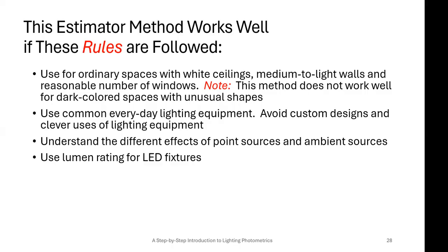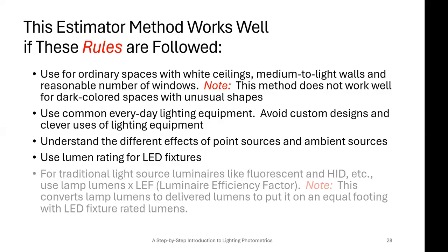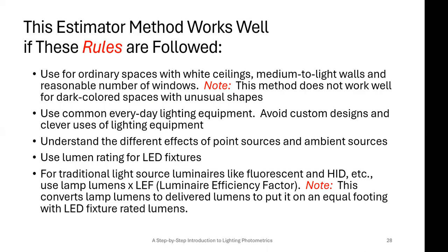And the lumen ratings are for LED fixtures. For traditional light sources, you can back this out and you have to use a luminaire efficiency factor, so you account for the light that's trapped. But today, most everything is LED, so you're probably not going to run into that.